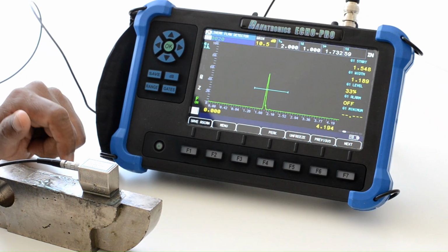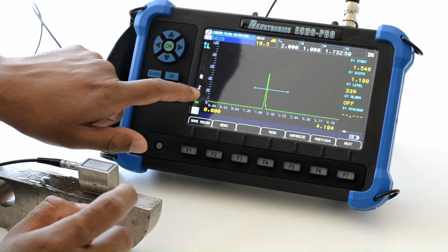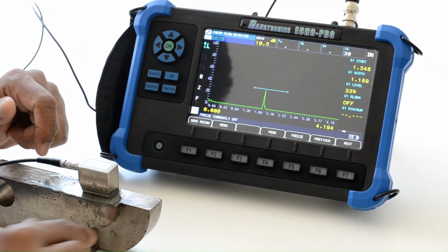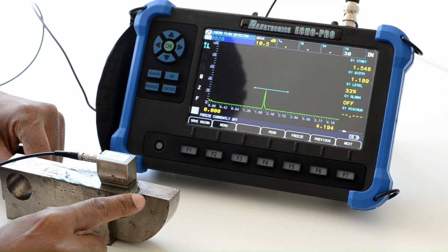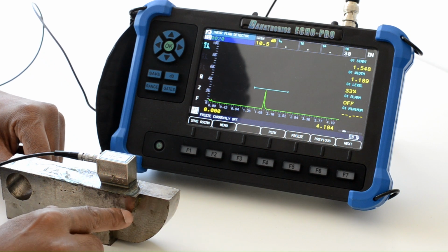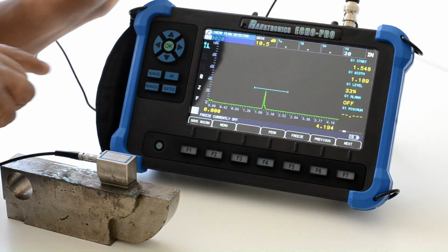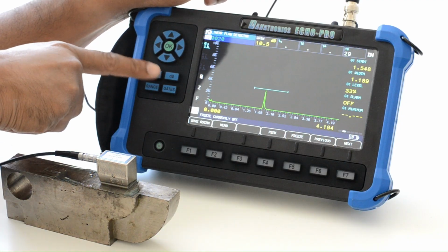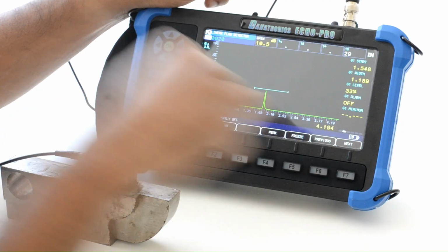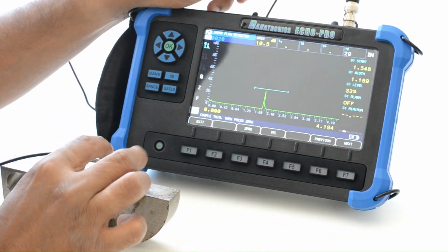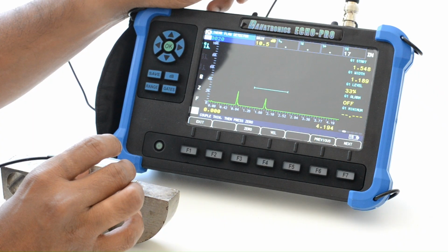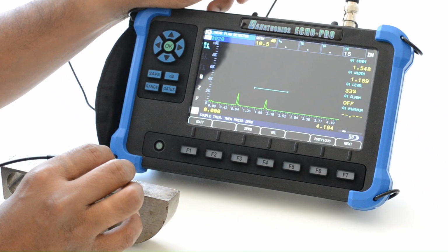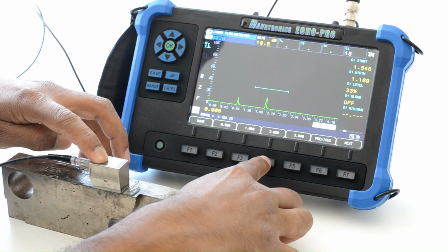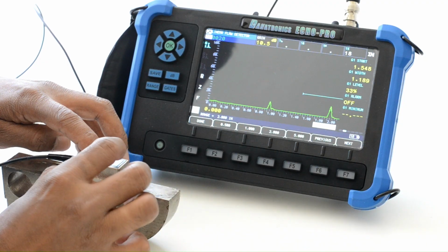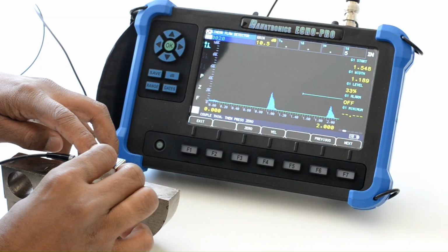I'll just show you around how to do a normal calibration. So for calibration, as you know, I've got a block which has a 1 inch radius and a 2 inch radius. So I will take this reference calibration block for doing a calibration. Let me go to the menu, select the calibration, and come over to a point where you can see both the echoes, the 1 inch and the 2 inch echo. So what I will do, I will take a range which is more suitable for this. Probably 2 inch range will be more suitable. And then I will press the peak so that I know where the peak is.